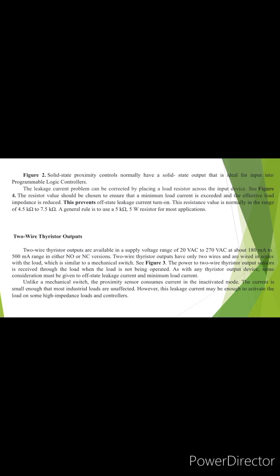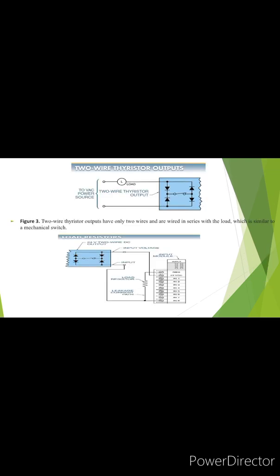Unlike a mechanical switch, the proximity sensor consumes current in the inactivated mode. The current is small enough that most industrial loads are unaffected. However, this leakage current may be enough to activate the load on some high impedance loads and controllers. This is Figure 3. Two-wire thyristor output.